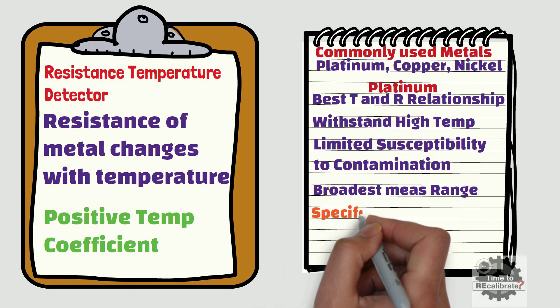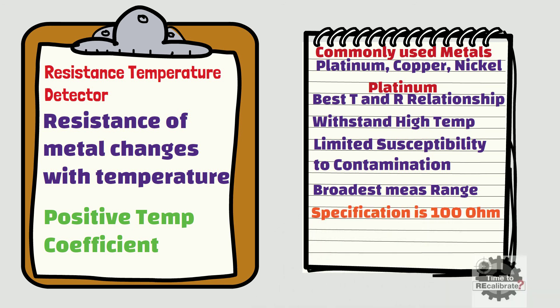The most common RTD specification is 100 ohms, which means that at 0 degrees Celsius the RTD element should demonstrate 100 ohms of resistance.